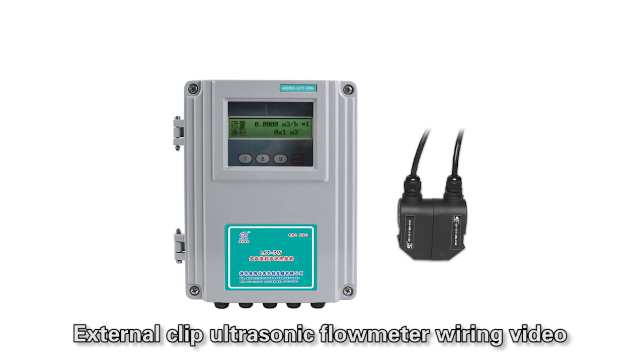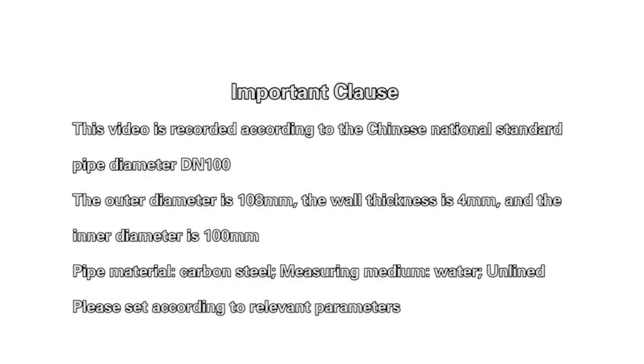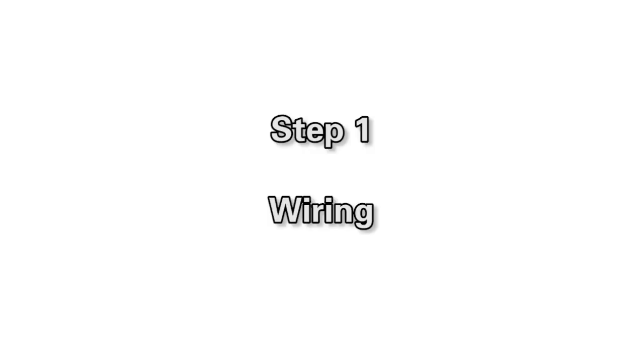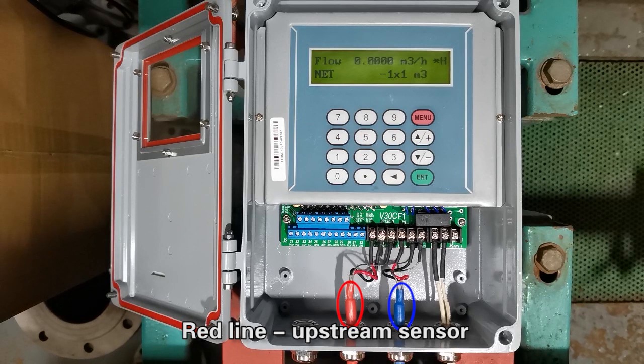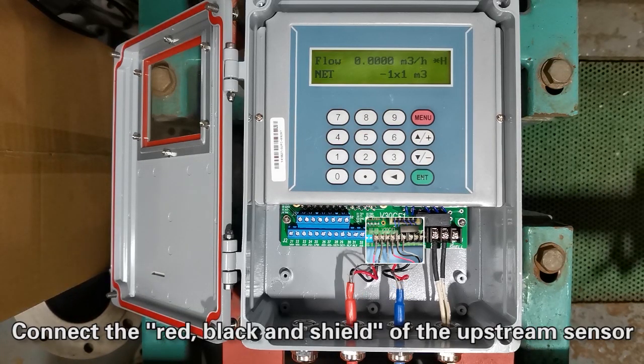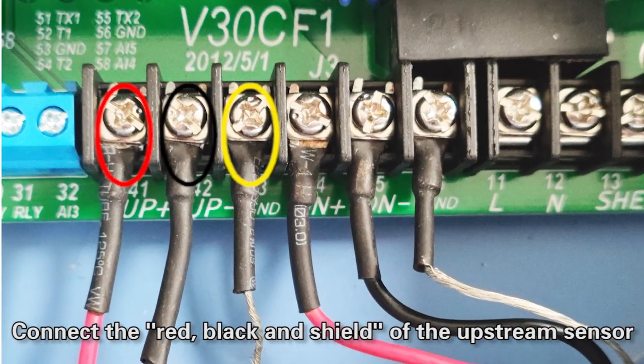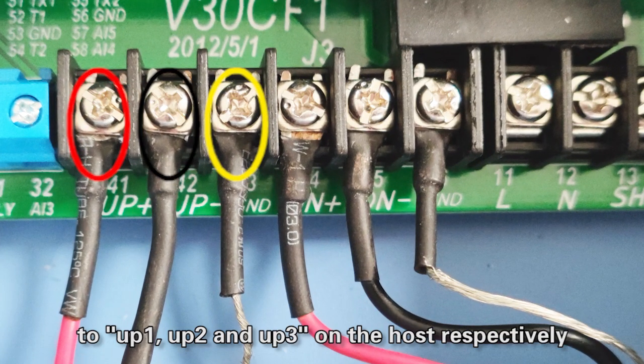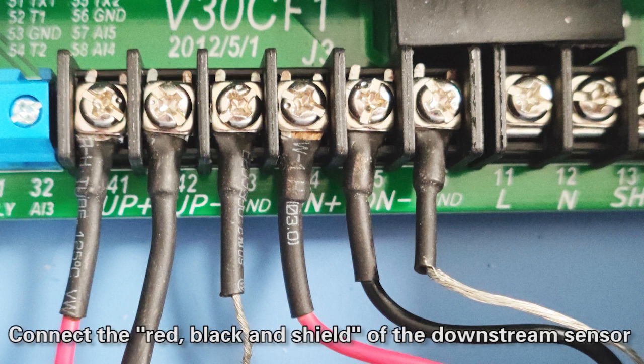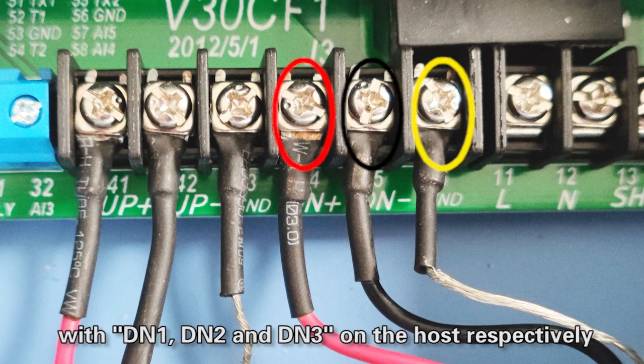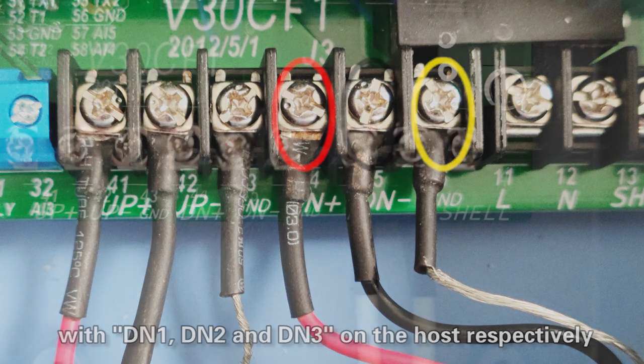External clip ultrasonic flowmeter wiring video. Step 1. Wiring. Red line upstream sensor. Blue line downstream sensor. Connect the red, black and shield of the upstream sensor to UP1, UP2 and UP3 on the host respectively. Connect the red, black and shield of the downstream sensor with DN1, DN2 and DN3 on the host respectively.